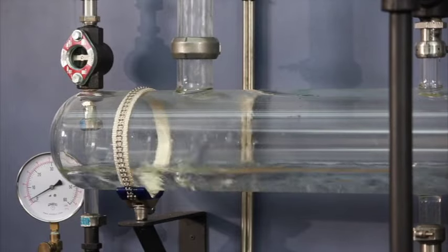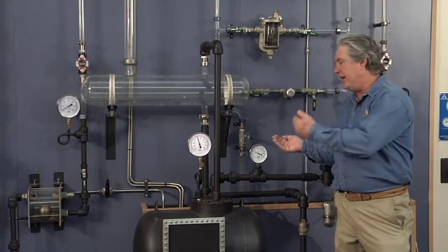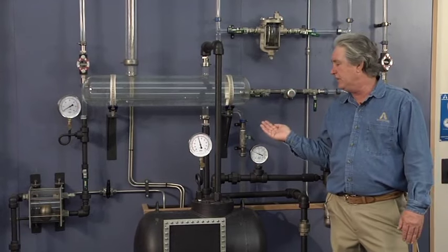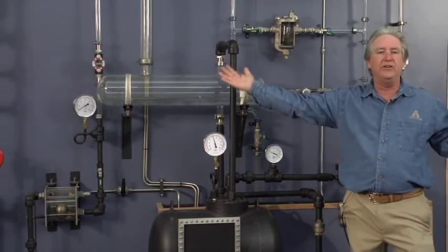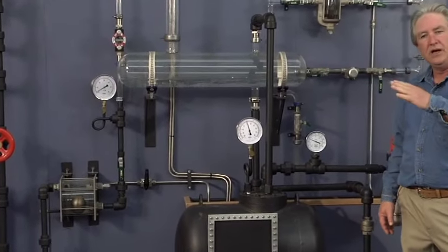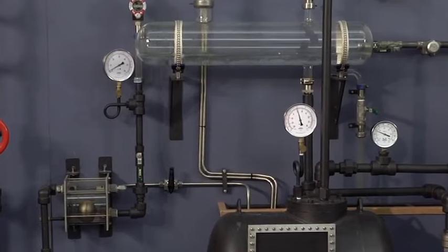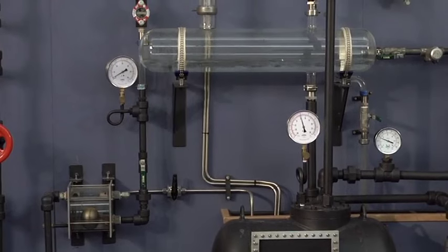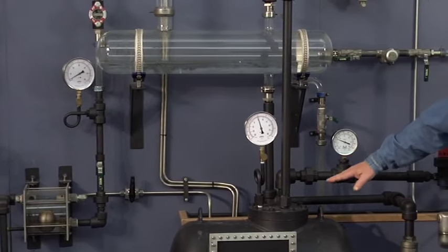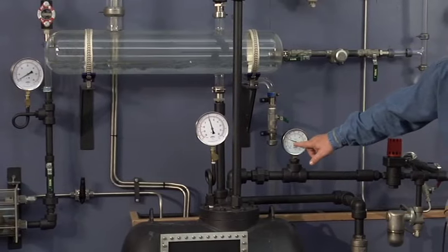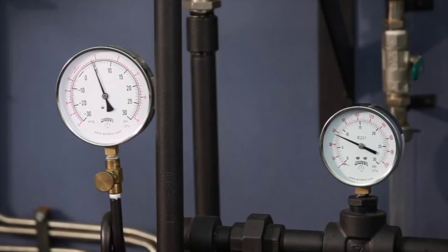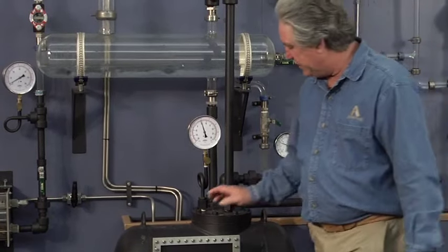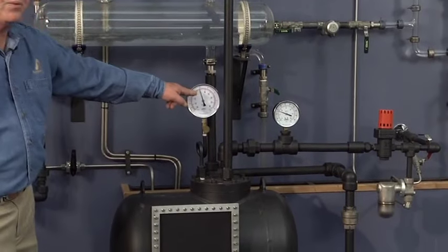Once we go through this pump out cycle, we'll go ahead and cycle the exchanger to go into vacuum and show you that it still basically allows you 100% turn down on the rates and the variables by allowing it to drain regardless of what that pressure is. Note that the steam pressure from the regulating valve going into the pump trap system that we have is set at about 8 pounds, okay? So we're feeding about 8 pounds into the pump. Note that now the pressure is up to about 6.